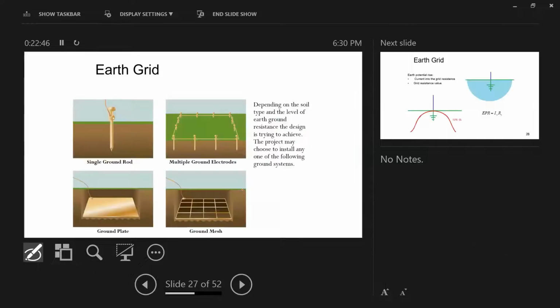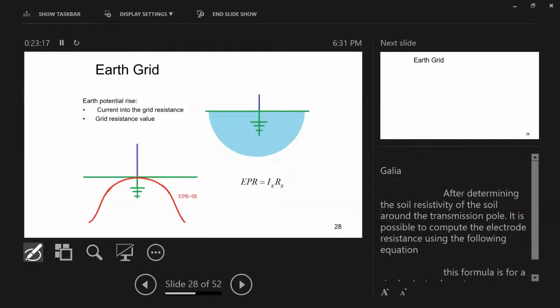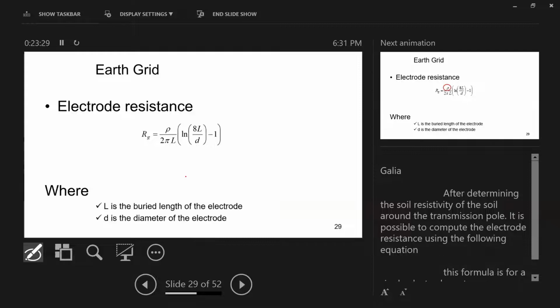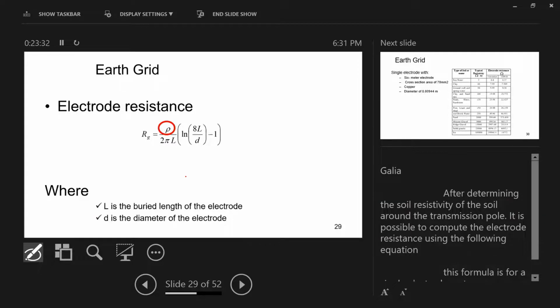And the earth grid is usually made of either a single electrode, or a combination of mesh and electrode, or mesh. If you have a very high soil resistivity, by the way, under the current standard, it's not recommended to have a high voltage infrastructure substation without having an electrode, at least one or two. So they don't like to have only mesh. They like to always have an electrode driven down into the ground. So guys, what happens when you have an earth potential rise? When I have an electrode driven down, the resistance of the electrode depends on your soil resistivity. That's the soil resistivity of the ground. You will determine your RG. This RG will determine your EPR.